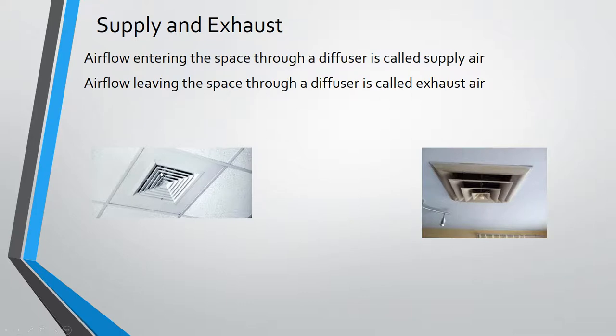But with that being said, that's how I think through if this was a supply or exhaust. That doesn't really matter, though. I just wanted to put that in there to give you guys a view of what supply and exhaust diffusers look like and how they can look very similar and how you shouldn't use them to determine things. But what you should understand is that airflow entering the space through a diffuser is called supply air. And airflow leaving the space through a diffuser is called exhaust air. Now, it may simply be returning to the air handler. It may be actually exhausting to the outside. It doesn't really matter. It's still called exhaust air.